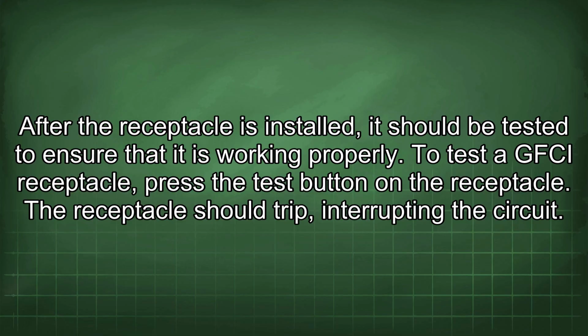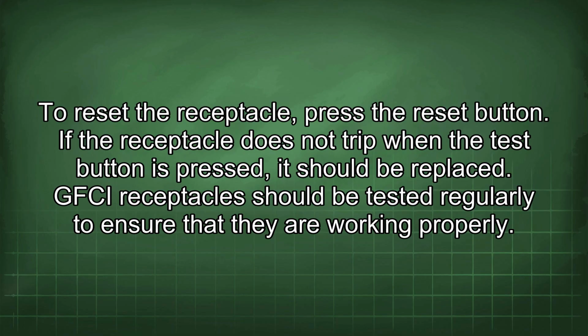To test a GFCI receptacle, press the test button on the receptacle. The receptacle should trip, interrupting the circuit. To reset the receptacle, press the reset button. If the receptacle does not trip when the test button is pressed, it should be replaced.